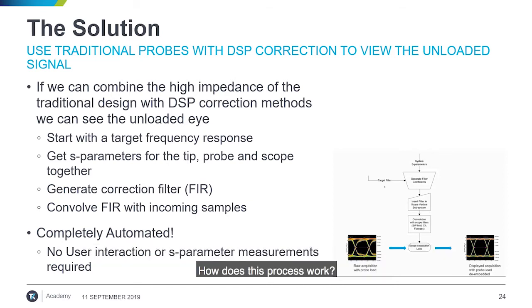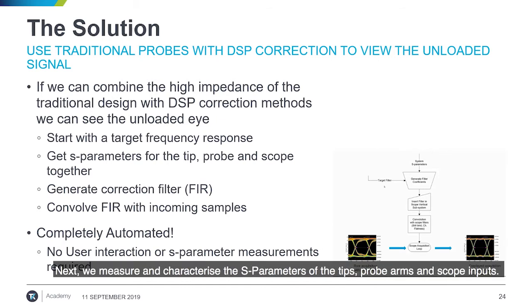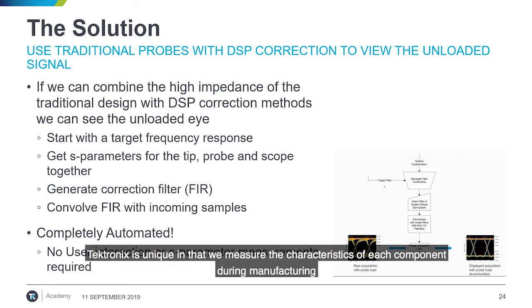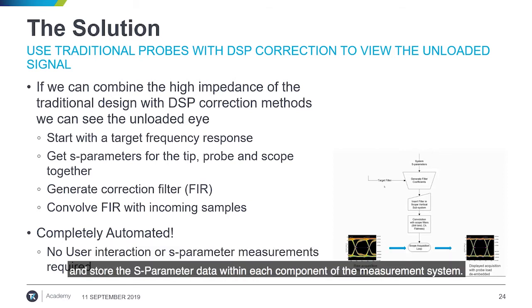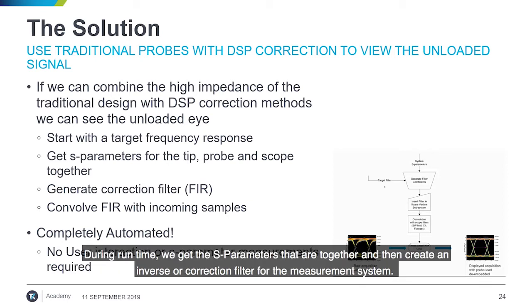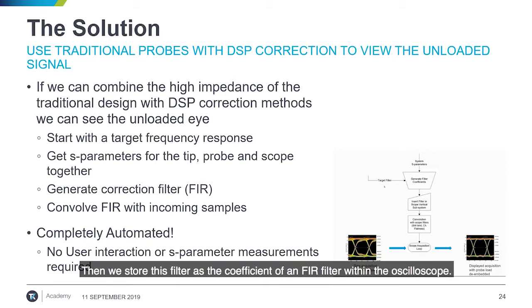How does this process work? First, we start with a frequency response that we desire. Next, we measure and characterize the S parameters of the tips, probe arms, and scope inputs. Tektronix is unique in that we measure these characteristics of each component during manufacturing and store their S parameter data within each component of the measurement system. During runtime, we cascade the S parameters data together and then create an inverse or correction filter for the measurement system. Then we store this filter as the coefficients of an FIR filter within the oscilloscope.